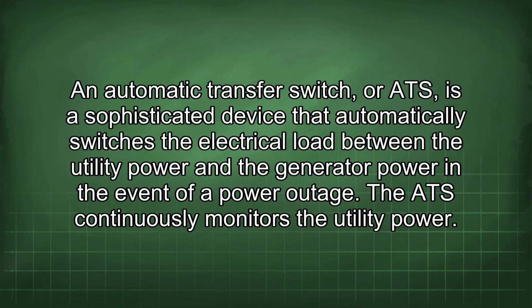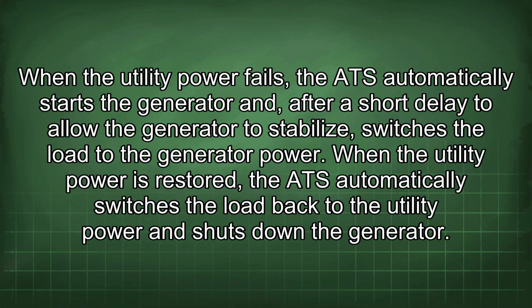An automatic transfer switch, or ATS, is a sophisticated device that automatically switches the electrical load between the utility power and the generator power in the event of a power outage. The ATS continuously monitors the utility power. When the utility power fails, the ATS automatically starts the generator and, after a short delay to allow the generator to stabilize, switches the load to the generator power.